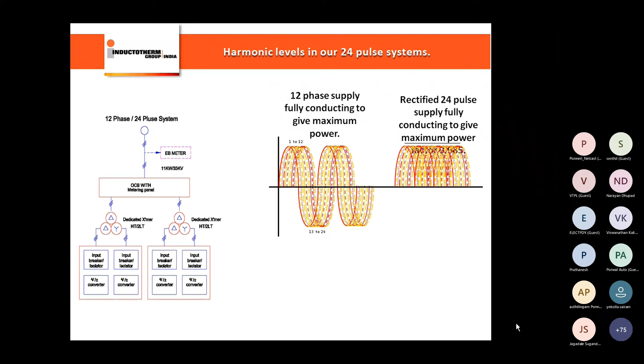For instance, in Tamil Nadu, the norms of the electricity board department are that if the harmonics of current are not maintained at 8% and voltage at 5%, per the IEEE 519 norms or the TANGEDCO norms, they have to pay a penalty of about 15% on their total electricity board bill. For instance, if the EB bill in a month is about 1 crore, they have to pay about 15 lakhs. So controlling harmonics in the overall plant is very, very, very essential.